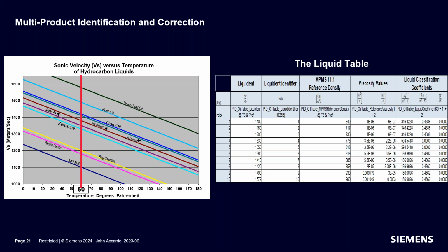And so what the meter will do, it will measure the actual speed of sound of the product. It will correct it to 60 degrees. It will then go to the lookup table, find out what liquid it is, determine what the density is at 60 degrees so that you can do standard volume correction. It will also determine what the viscosity is at the current temperature. So it's calculating the correct Reynolds number, which remember is a function of viscosity and flow rate. And so even though you could have different products in the pipe, the meter can identify them and do the corrective action to give you accurate measurement, regardless of what that liquid is.